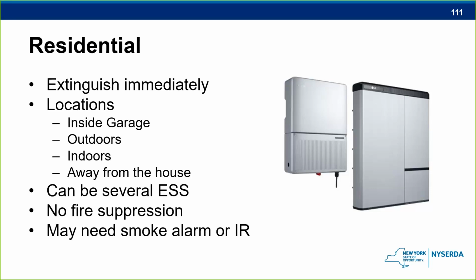The locations where they can be found are inside the garage and on the outside of the building itself. There is no signage for firefighters to know whether this thing is out there, but they should start to be aware that these things will start popping up on private dwellings. They will be outdoors in private dwellings too, so make sure that you have clear access to them if you do need to stretch a line to the rear of the house to get water on the energy storage system that's on the back of the wall. But they also can be indoors, right? They can be indoors in utility closets.